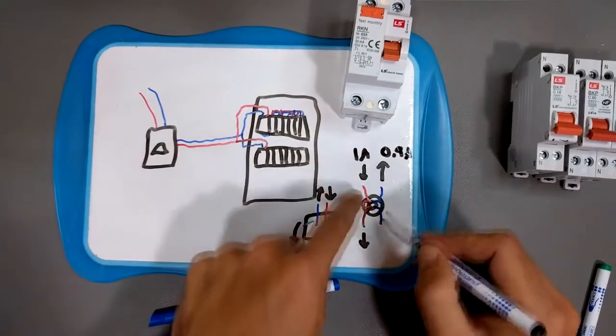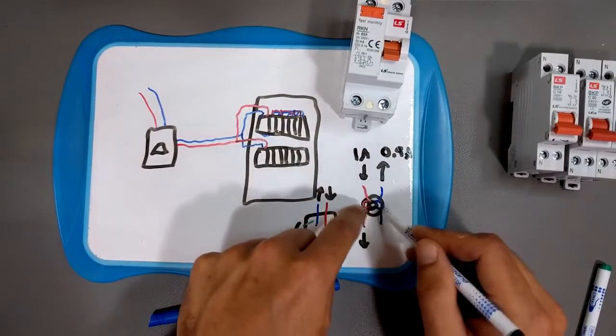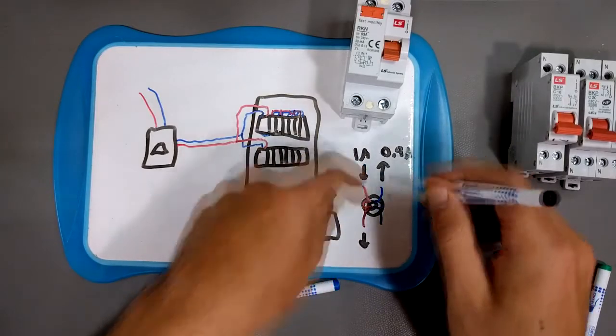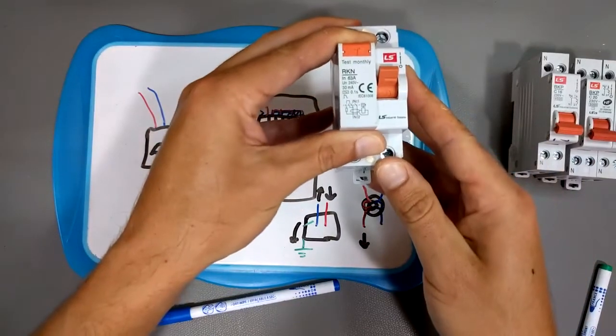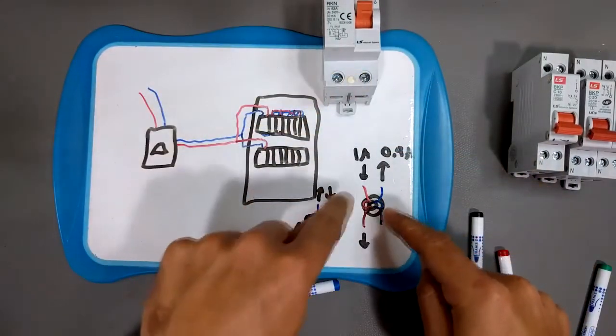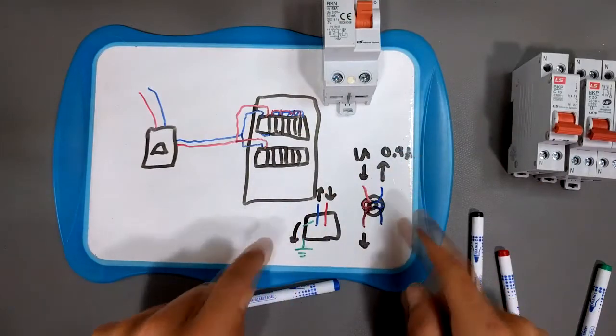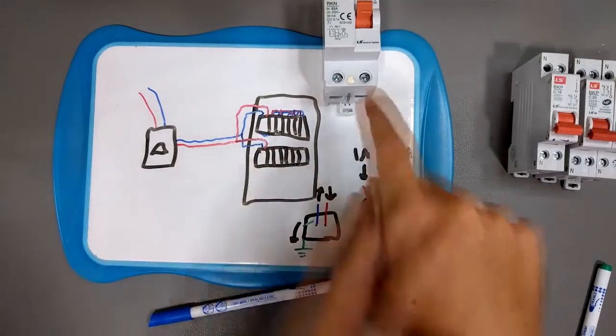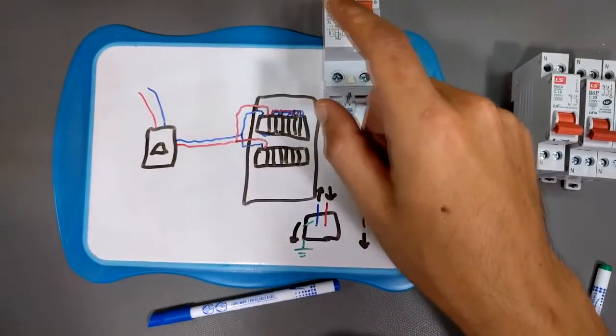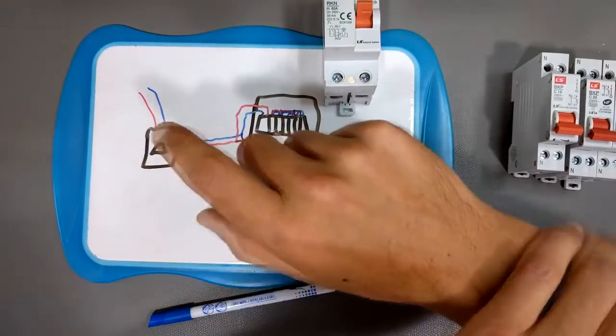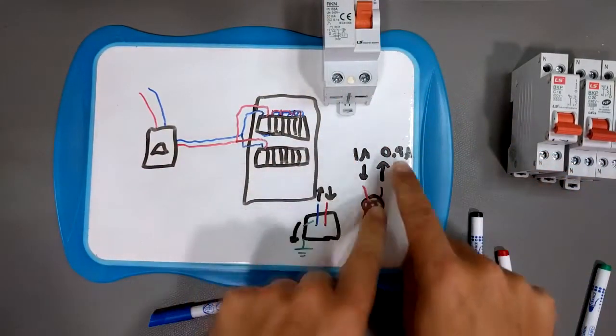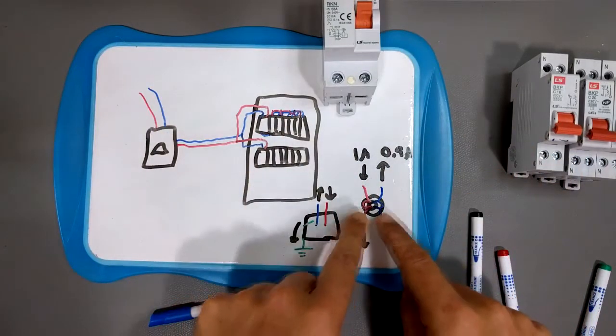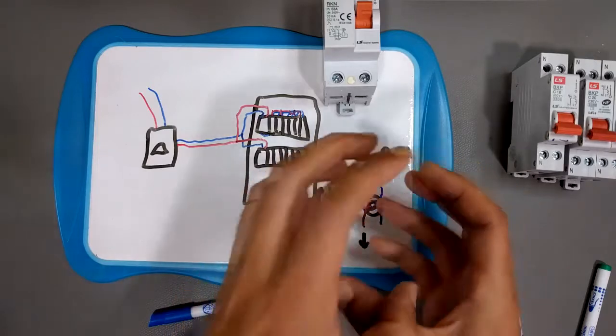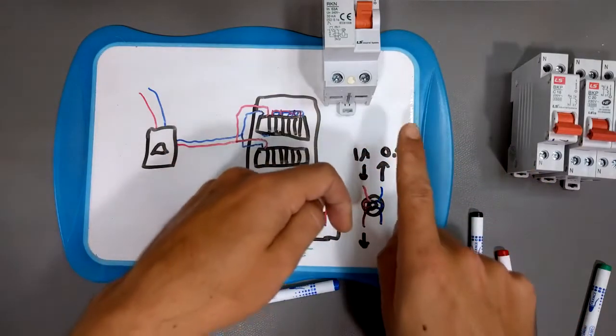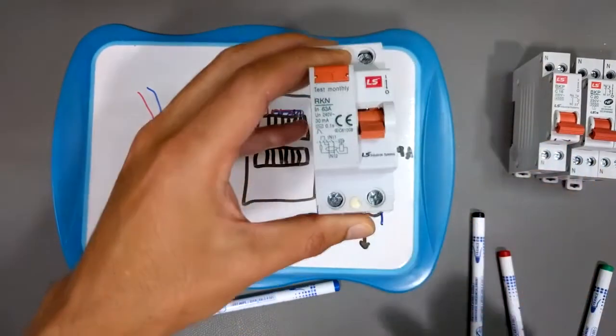That's what this device detects, because the current is going through this little toroid, basically coils of wire on a toroid. When the currents are equal, this guy stays on. But when there's a differential in the current, meaning some current is leaking to ground, or maybe you touch one of the wires and you become the path to ground through your arm and hopefully not your heart, through your foot into the ground, or you're touching a grounded surface - that's a leakage current, meaning current in and current out won't be equal. Because this is a magnetic device, the magnetic field becomes unbalanced, and that means this guy will trip.